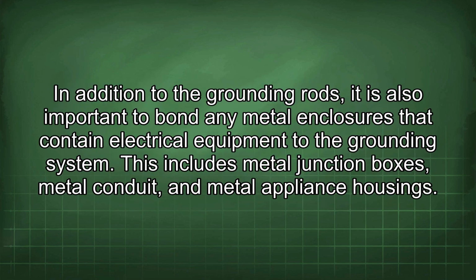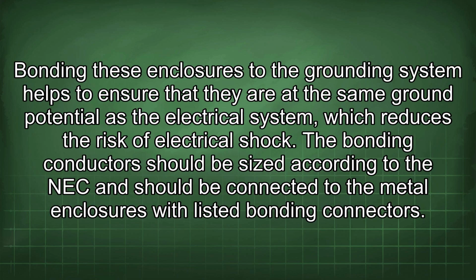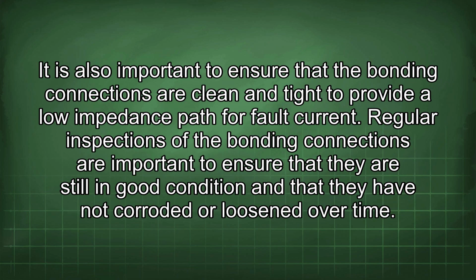In addition to the grounding rods, it is also important to bond any metal enclosures that contain electrical equipment to the grounding system. This includes metal junction boxes, metal conduit, and metal appliance housings. Bonding these enclosures to the grounding system helps to ensure that they are at the same ground potential as the electrical system, which reduces the risk of electrical shock. The bonding conductors should be sized according to the NEC and should be connected to the metal enclosures with listed bonding connectors. It is also important to ensure that the bonding connections are clean and tight to provide a low impedance path for fault current.